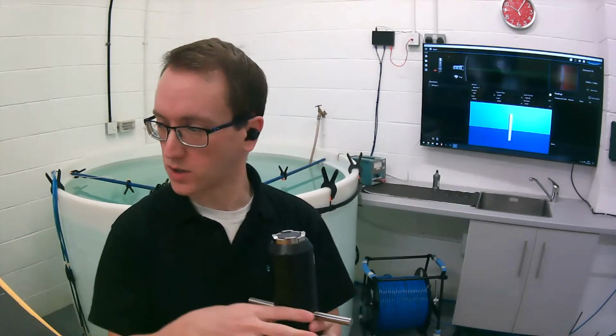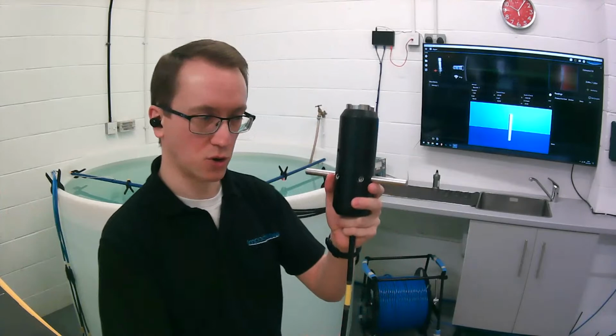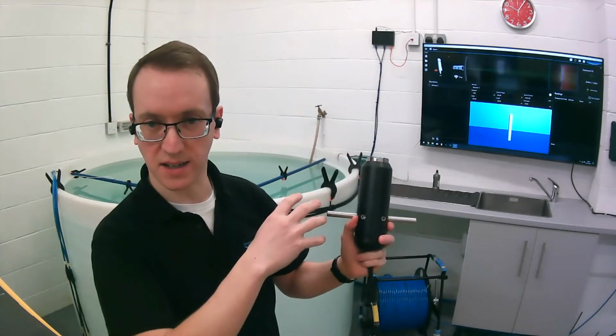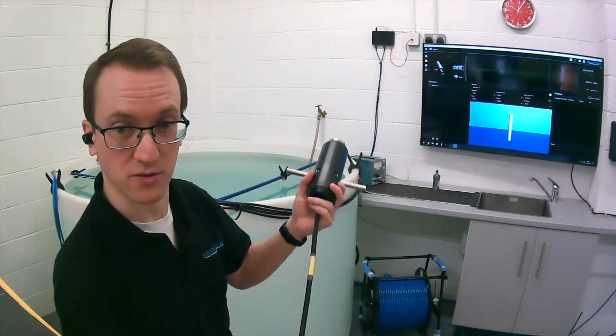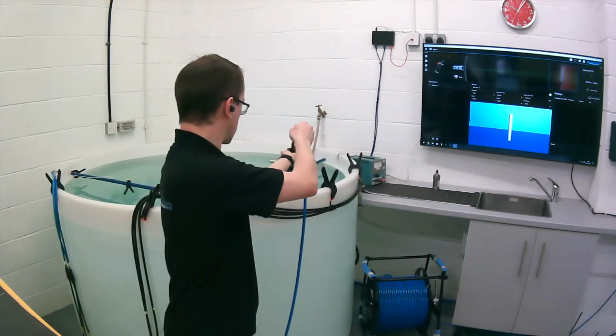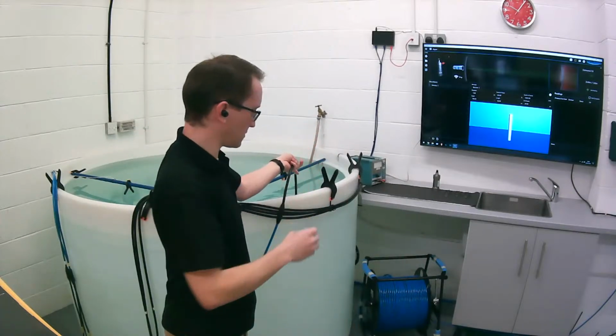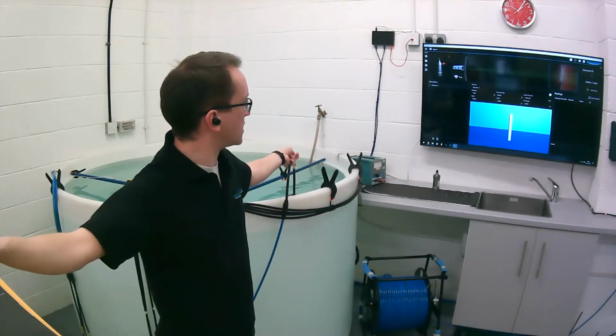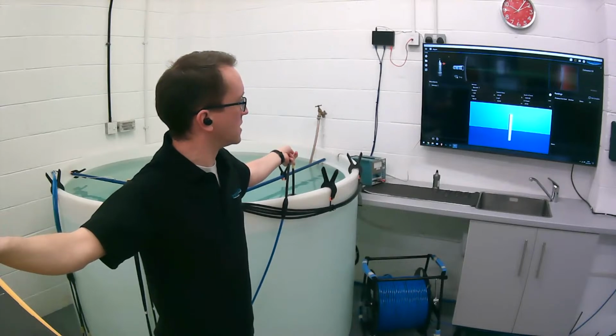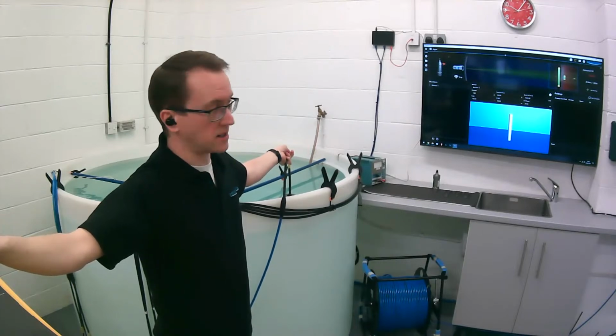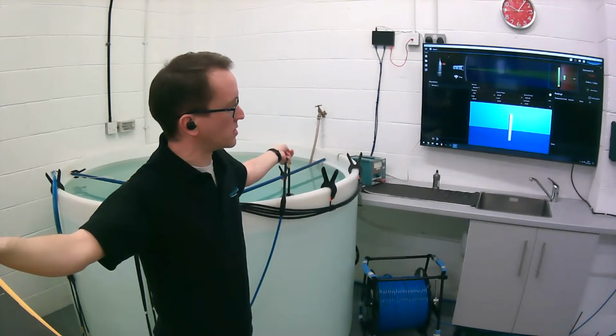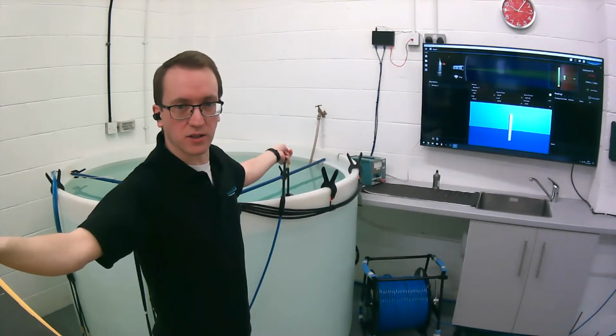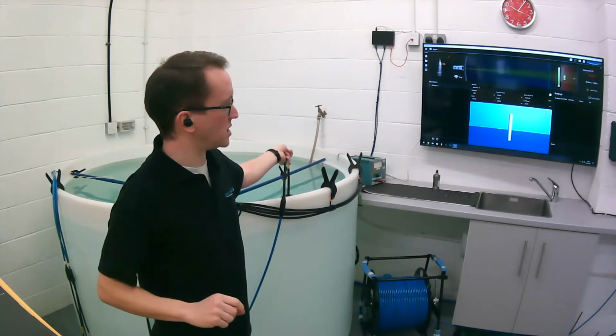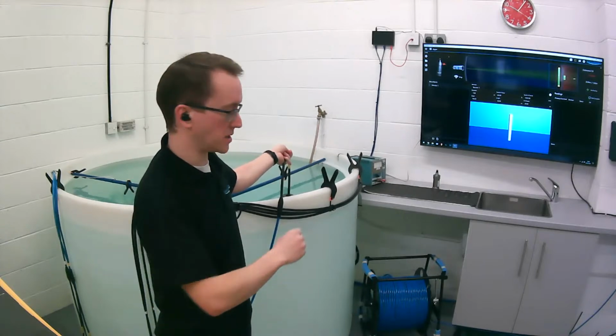So just to show you how this works, I'm just going to drop the probe into our test tank here to simulate a flooded member, just for ease of demo. So drop it in there. Then in the software, we click ping, and you can see we've got a return at about a meter value, which is the diameter of the member I've set up. So it's been classified as flooded.